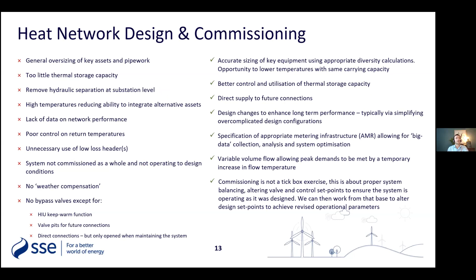And people say to me, oh, we do it because of water quality. Well, that suggests that you're just pushing the problem down the line and assuming that water quality is bad in a secondary connection. Bypass valves, we see them put in everywhere. Please avoid them. Please avoid low loss headers. So any questions on those, please get in touch.